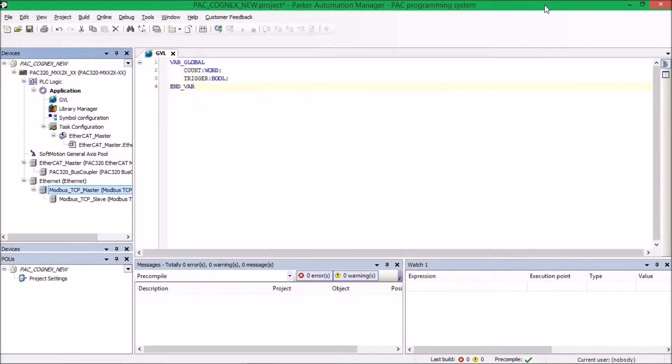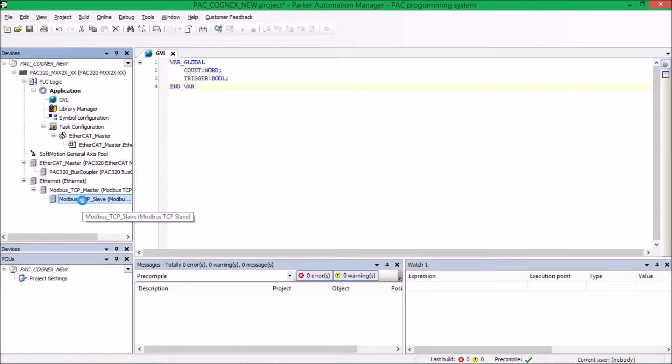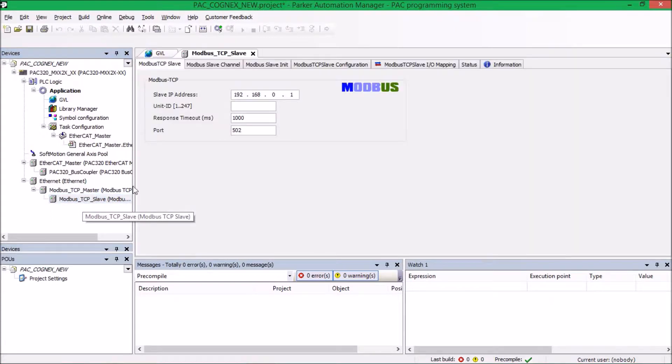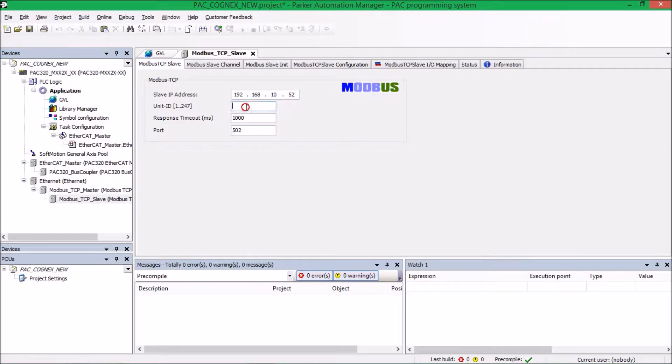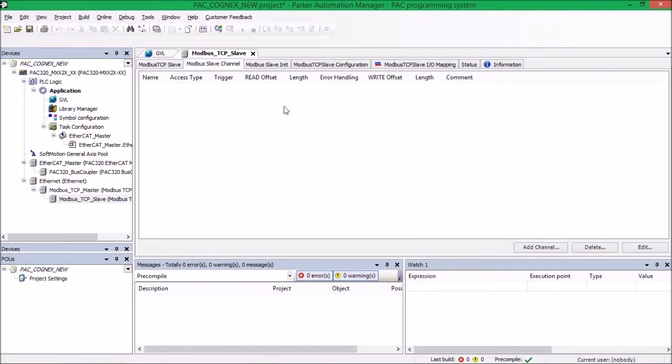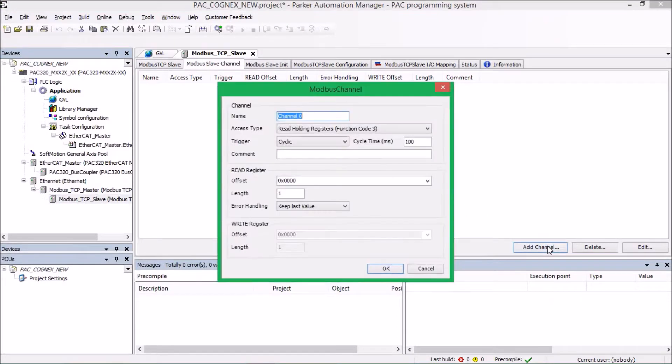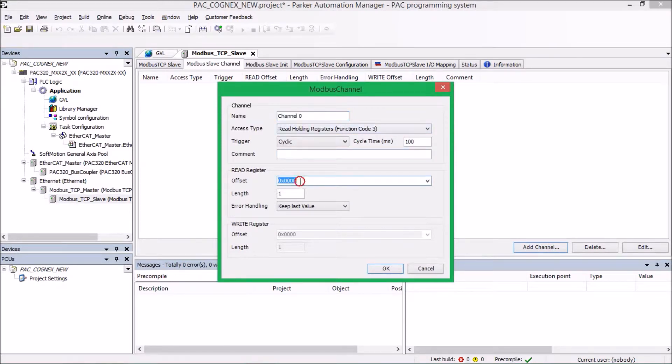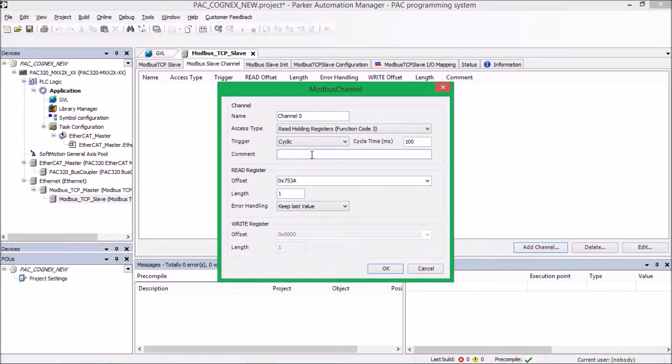So now what we need to do is we need to set up the Modbus TCP Slave and set up some channels. So we're going to give it the IP address of the Cognex, which we'll just say right now is 192.168.10.52. And it needs a unit ID. This can be whatever you'd like. I just select one. Now we're going to add some channels. One channel is going to be reading in the blob count from the Cognex camera.